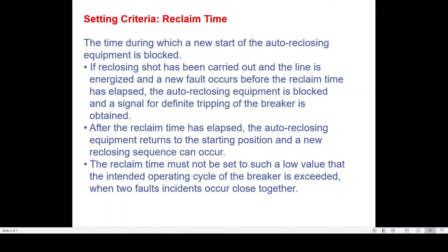If a reclosing shot has been carried out, the line is energized, and a new fault occurs before the reclaim time has elapsed, the autoreclosing equipment is blocked and a signal for definite tripping of the breaker is obtained. That means if there is a permanent fault or a fault within the reclaim time, your autoreclosure relay will issue a three-phase trip command. The second fault may be in any phase — Y, B, or R — but the autoreclosure relay will directly issue a three-phase trip command and the breaker will be in the lockout stage. After the reclaim time elapses, the autoreclosure equipment returns to the starting position and a new reclosing sequence can occur.